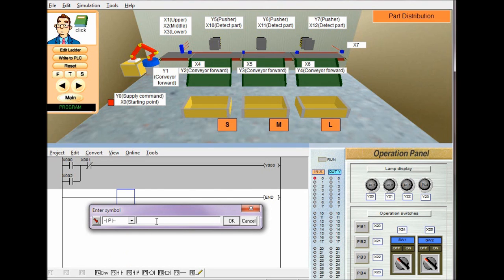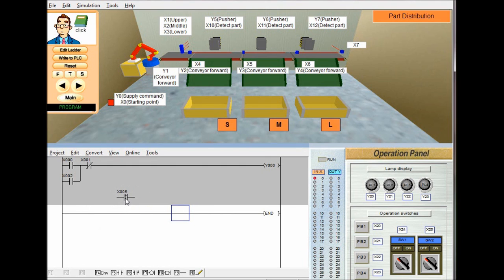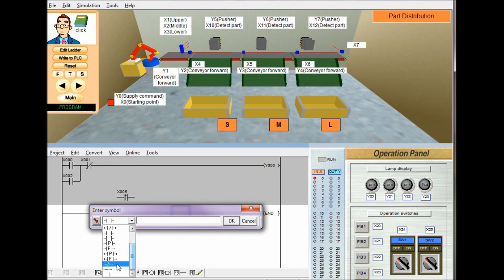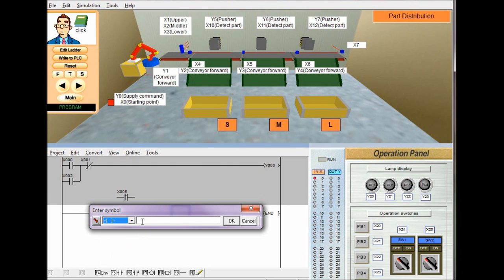There are also other contact types in Mitsubishi PLC. The P contact is a rising edge input contact — it is also named using X, for example X5. This means it sends only the rising edge of an input signal, regardless of whether it is continuous or discrete. Similarly, F is the falling edge contact. These are the major instructions available. Two symbols are used for making horizontal lines along with the rung, and one symbol for making vertical lines between rungs. There is also a command box bracket used for entering commands like resetting a counter or timer.